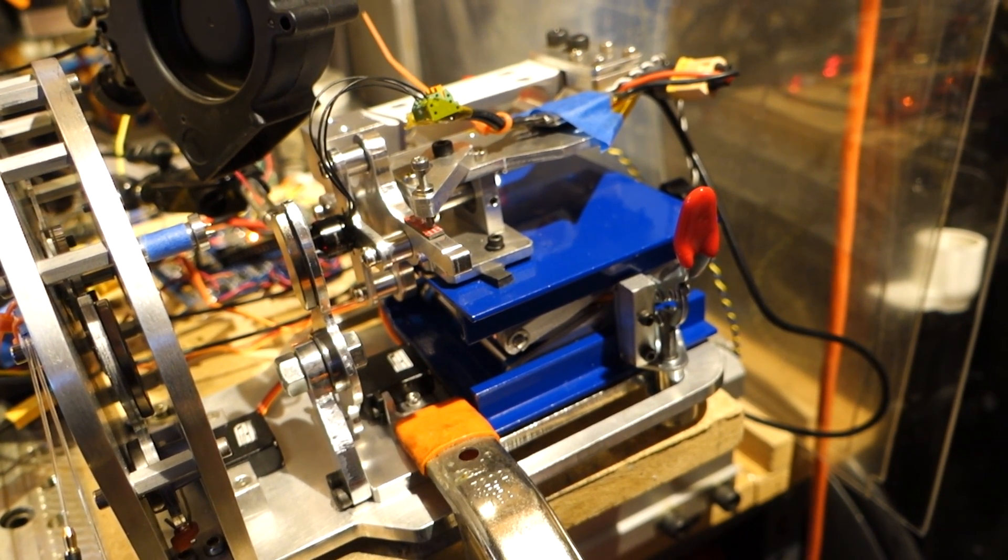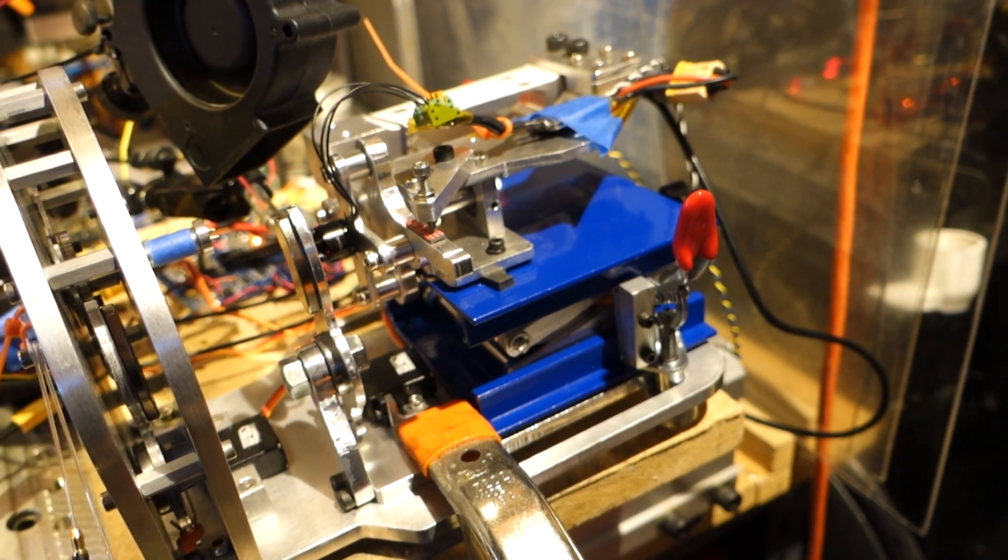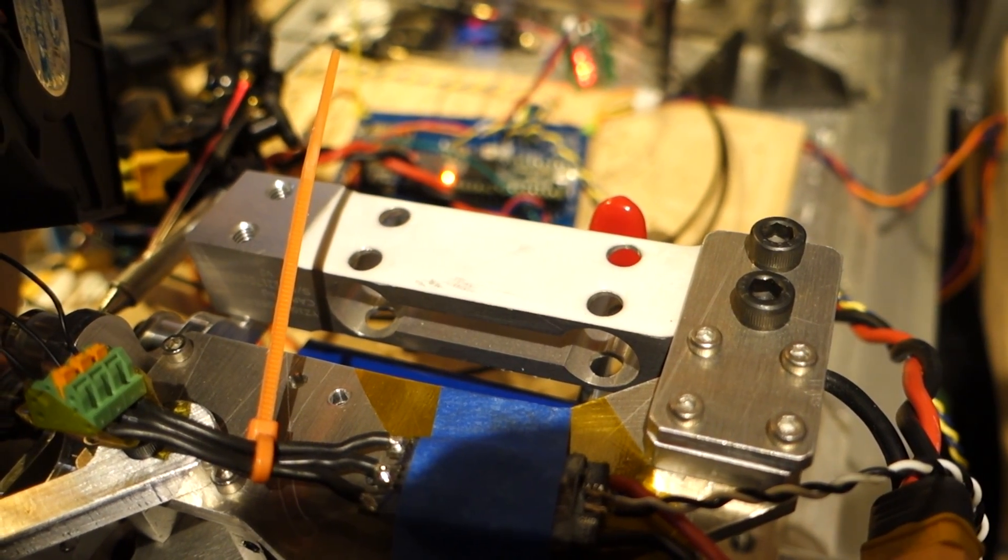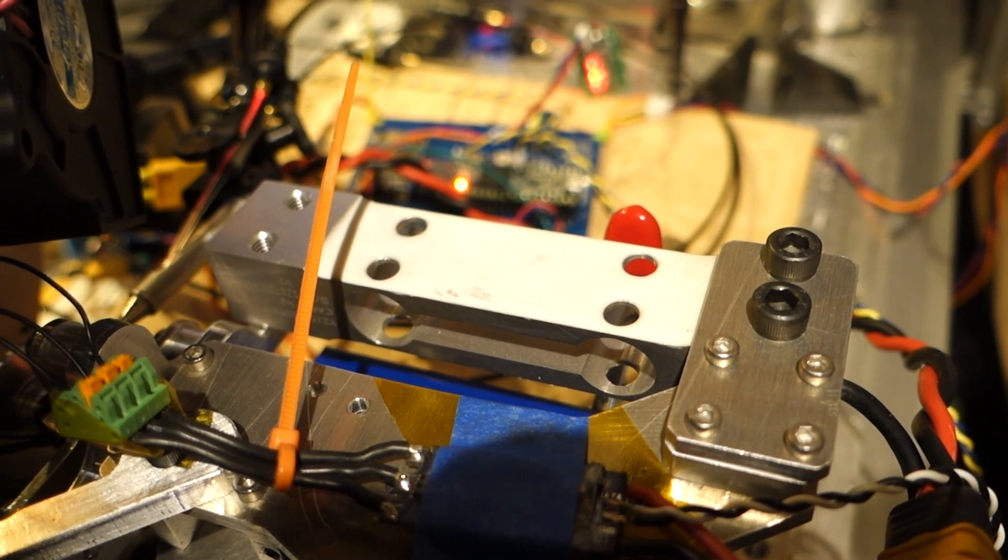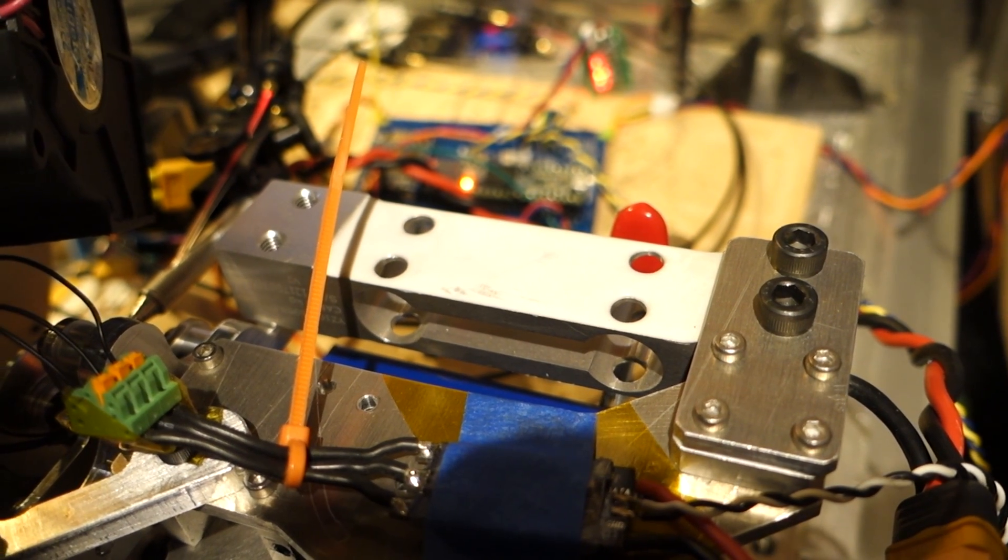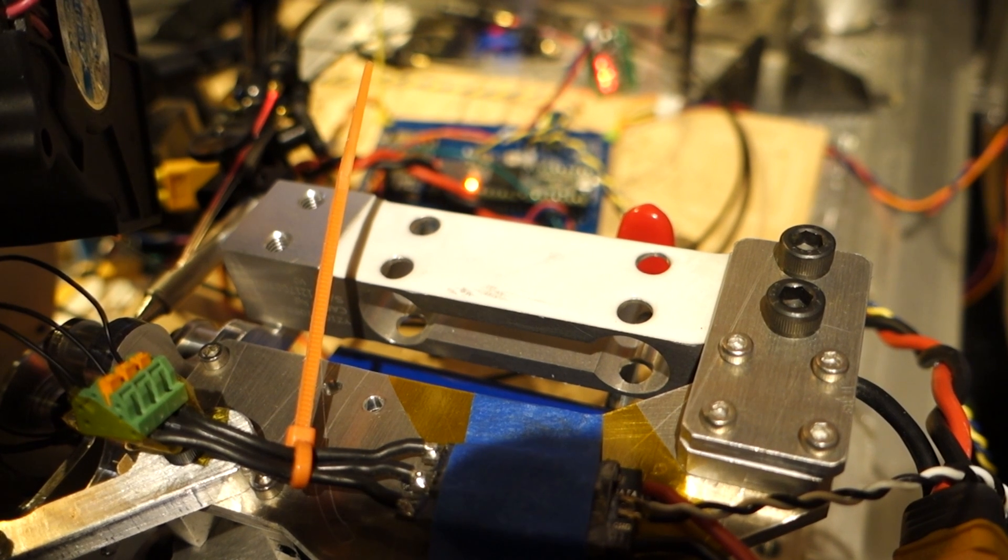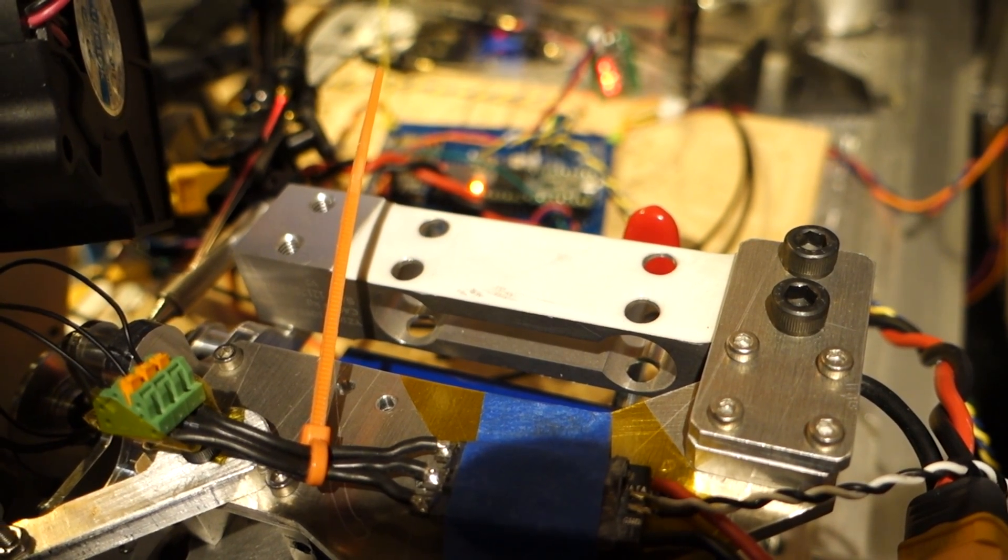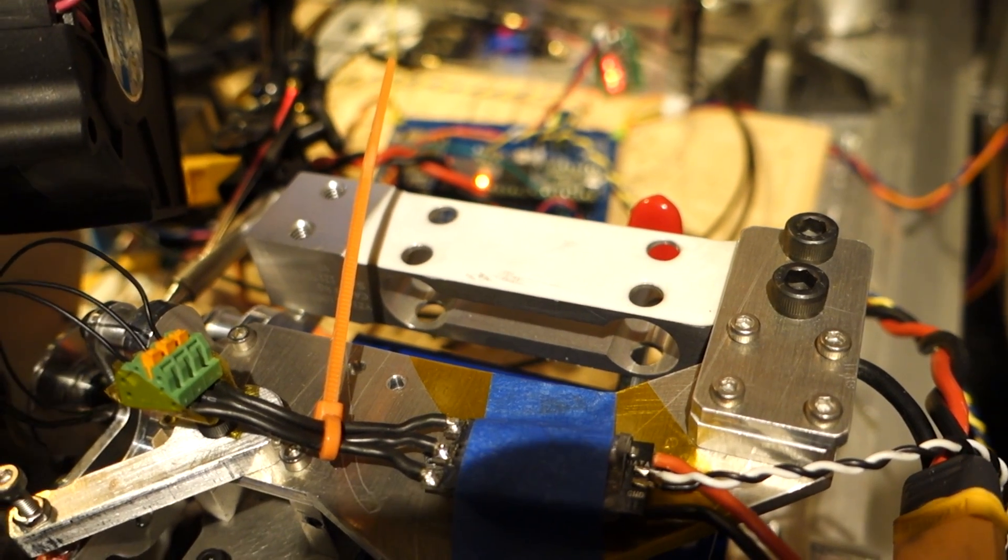The load cell is now totally rigidly mounted. Had too many problems with soft isolation material causing a lot of non-linearity in the readings, especially at low values. So everything is completely hard mounted now and they just soft filter the results to clean up any noise.